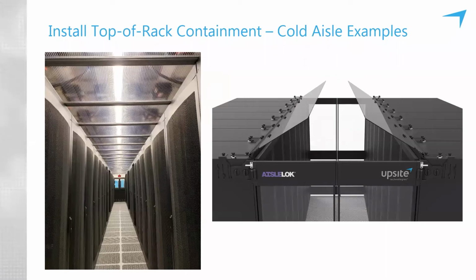All right, thanks, Lars. So I'll talk about the one on the right. So this is your kind of capped aisle in a cold aisle containment solution. So you're looking at a long aisle here. It's 20 cabinets on each side. They're wide cabinets. They're 32 inches wide each. The real nice feature for capping an aisle is cabinets that are the same height throughout the aisle on both sides. And if you've got that kind of skyline profile, there are easy ways to accommodate and end up with the same result.